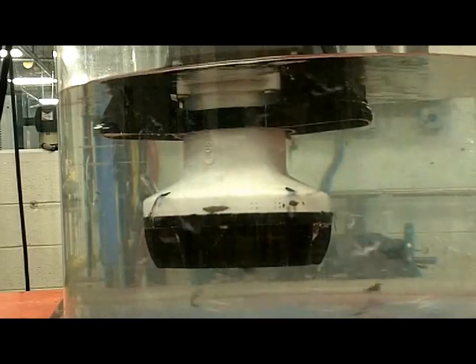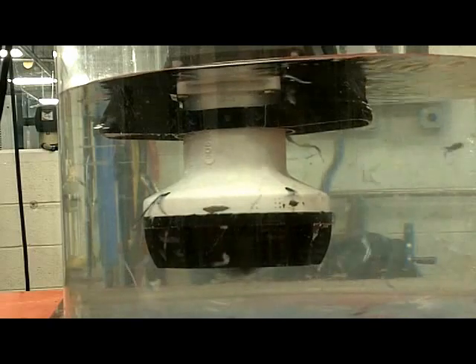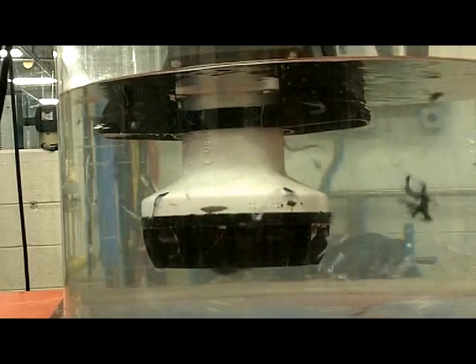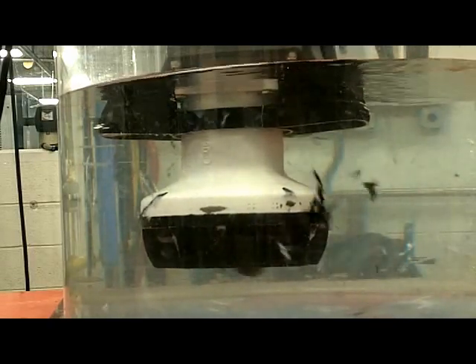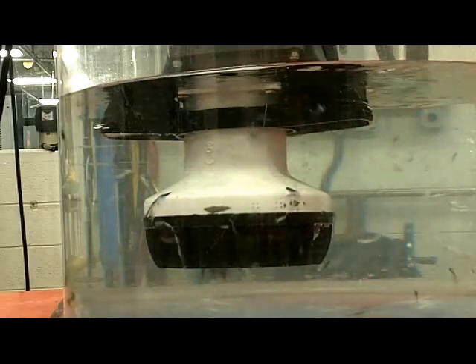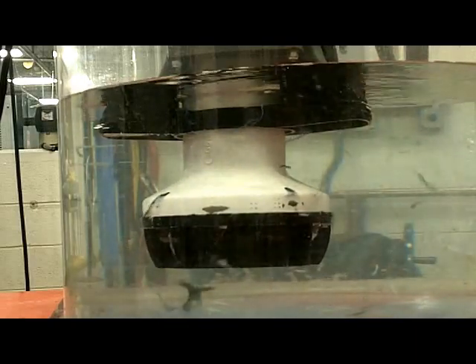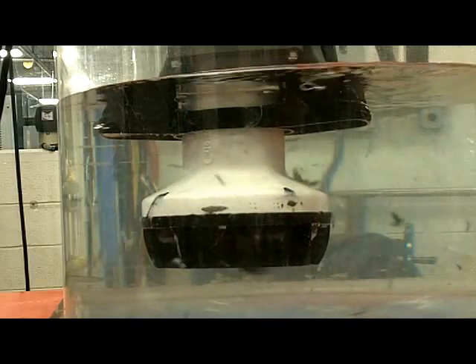These characteristics, namely gentle upward flow, high torque motor, and the fact that solids need not be ground immediately but can make multiple passes through the grinding zone, account for the reputation that E1 stations enjoy. They never jam.